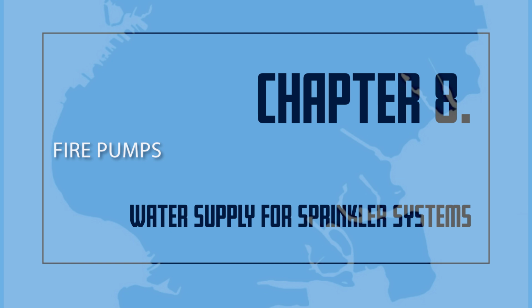This type of system gives an automatic water flow signal to the certificate of fitness holder when the pump must be started. Automatic fire pumps are usually needed where a high water demand may occur immediately. This demand may occur in a deluge system. The automatic fire pump is also used when someone is not always present to activate a manual pump.